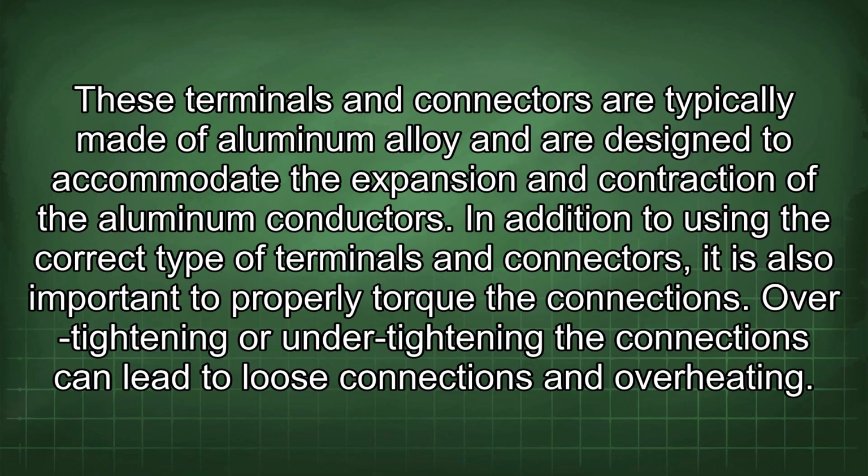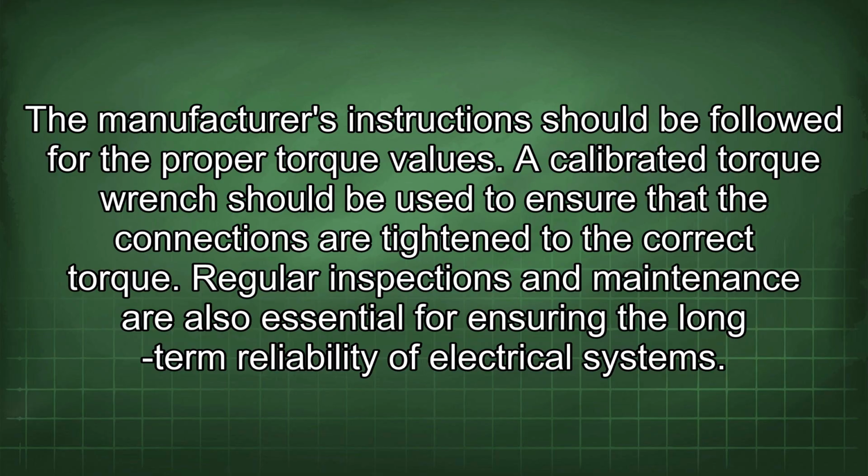of the aluminum conductors. In addition to using the correct type of terminals and connectors, it is also important to properly torque the connections. Over-tightening or under-tightening the connections can lead to loose connections and overheating. The manufacturer's instructions should be followed for the proper torque values.